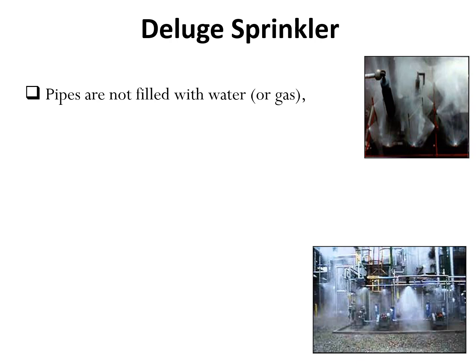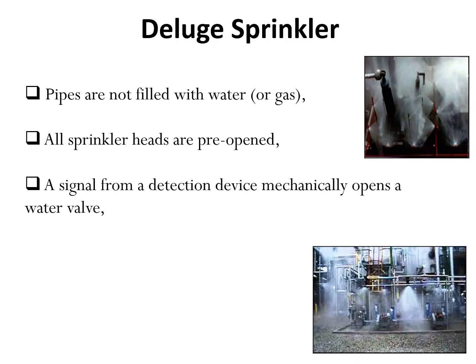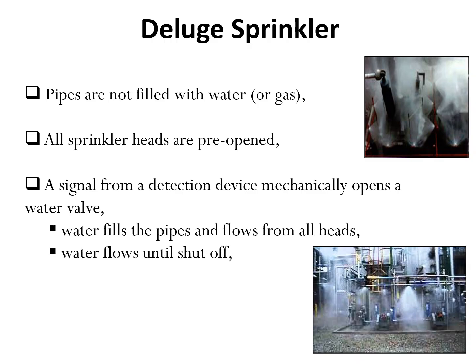Deluge sprinkler systems are mostly provided in large risk areas like transformer rooms. Here, pipes are not filled with water or gas. All sprinkler heads are pre-opened. A signal from a detection device mechanically opens a water valve. Water fills the pipe and flows from all heads, so it floods the area. Remember, in case of electrical apparatus being protected, first you have to manage to make the electricity off, then only the water system should work.